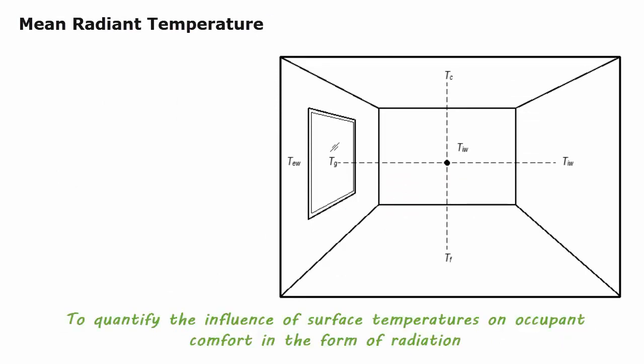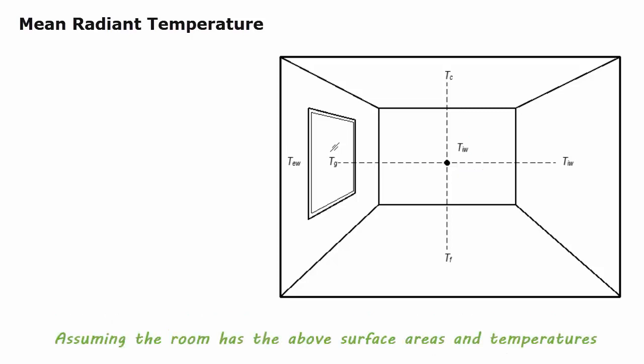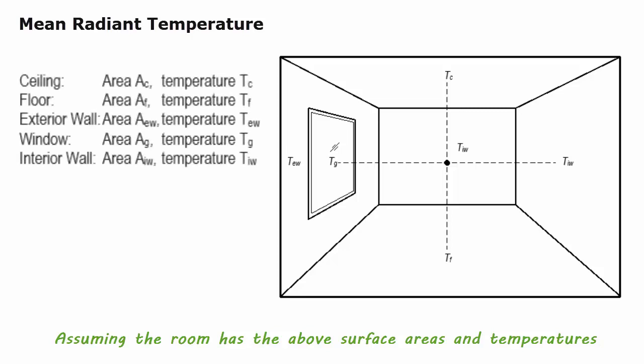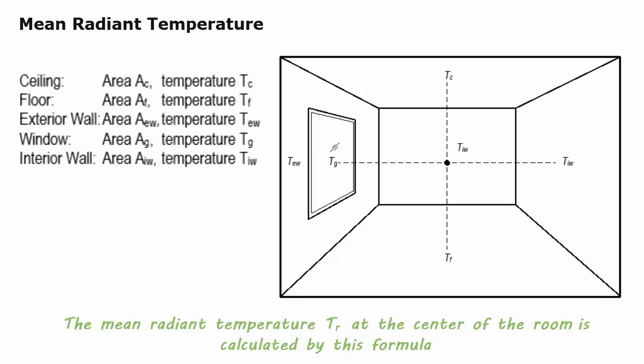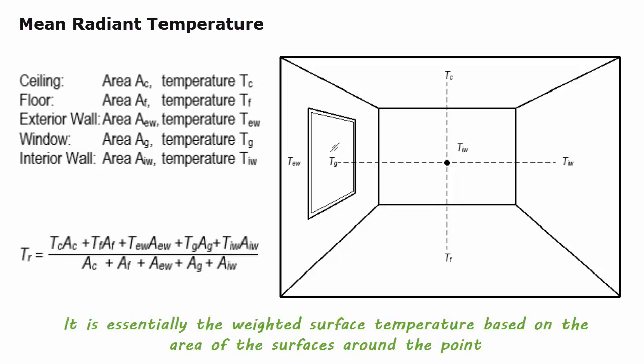To quantify the influence of surface temperatures on occupant comfort in the form of radiation, mean radiant temperature is used to measure the average temperature of the surfaces surrounding a point of interest. Assuming the room has known surface areas and temperatures, the mean radiant temperature TR at the center of the room is calculated by a weighted surface temperature formula based on the area of the surfaces around the point.